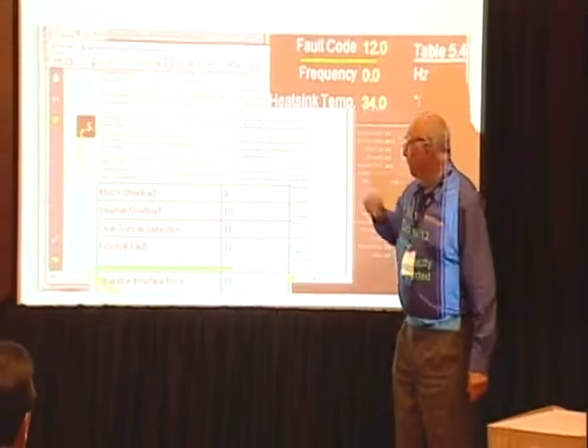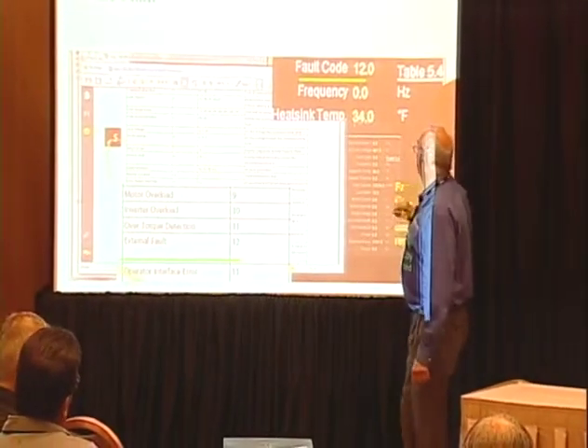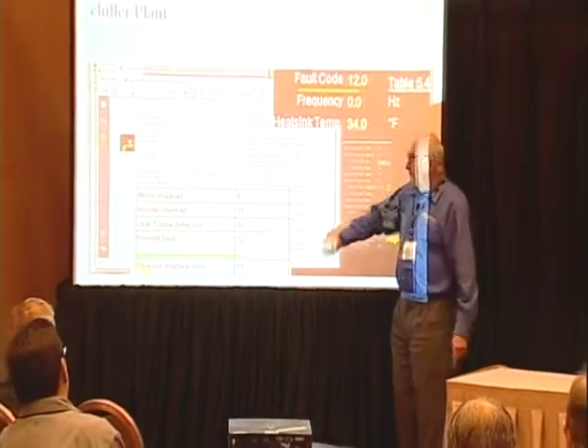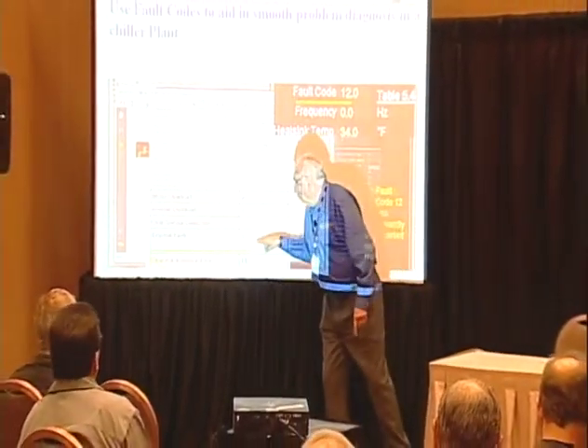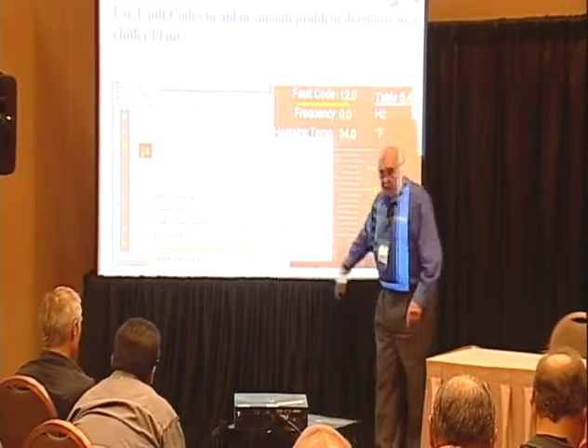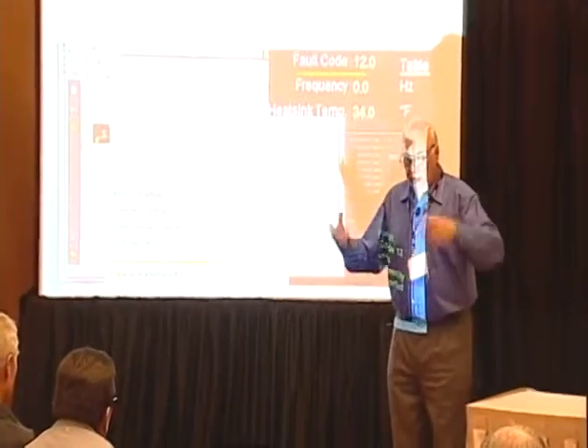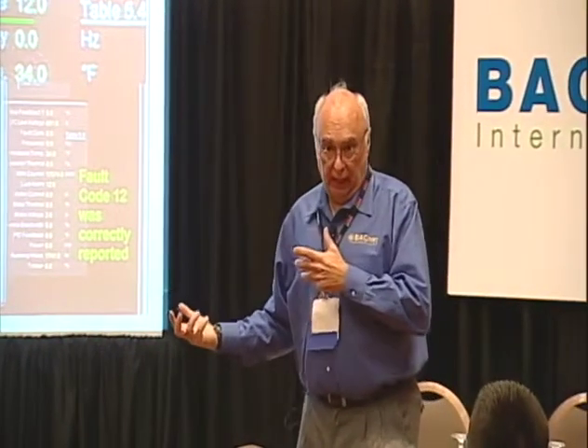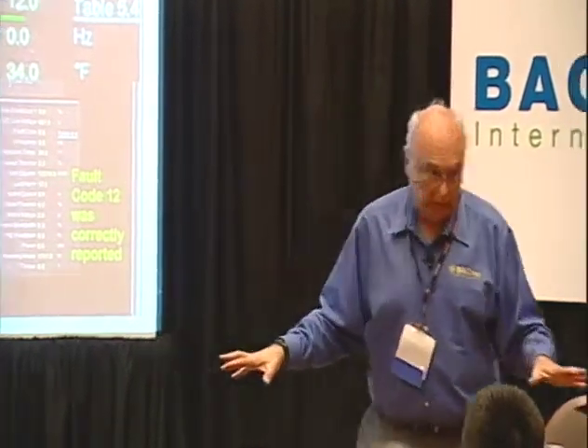So, these are fault codes that we generated during the commissioning process. So fault code 12 came in, and what the controls contractor did was, this document is a PDF of the BACnet troubleshooting guide for the chiller supplier. And so there's a link on the graphic that when you get a fault code, okay, you can open up the PDF document and see the fault code was an external fault. And then it'll give you instructions here, who to phone, is this a critical fault, do I have to shut the chiller down? Because some faults, the chiller will shut itself down and restart itself back up again. Other faults, it shuts it down until somebody goes there.